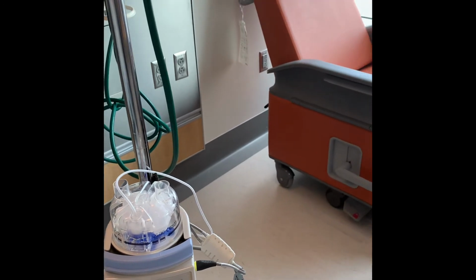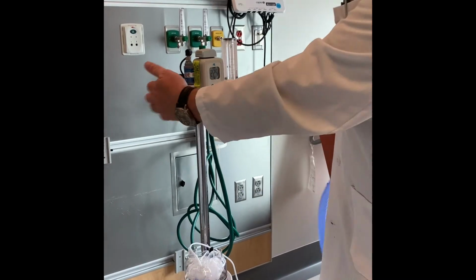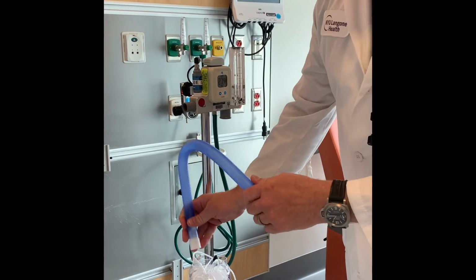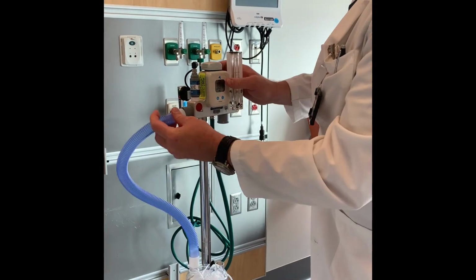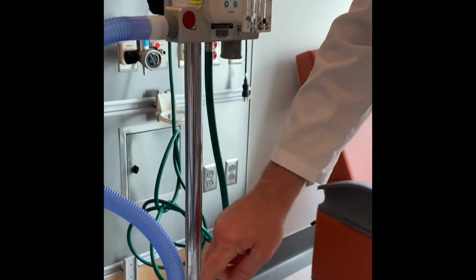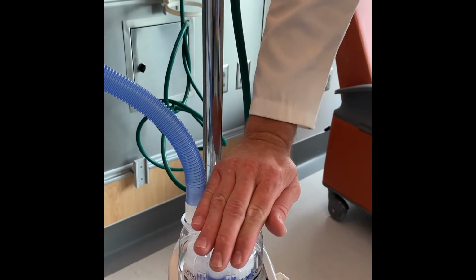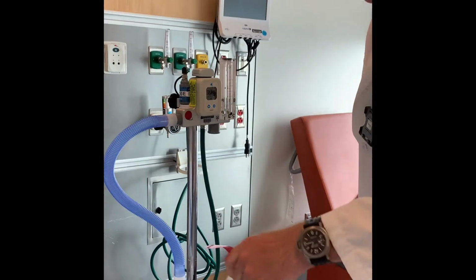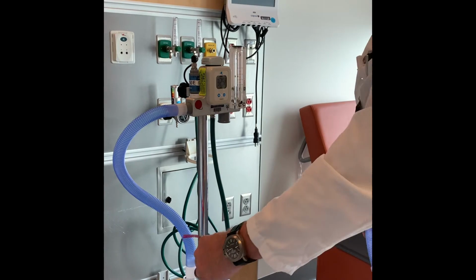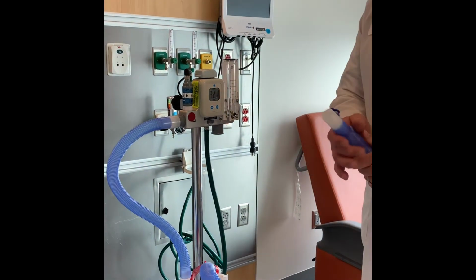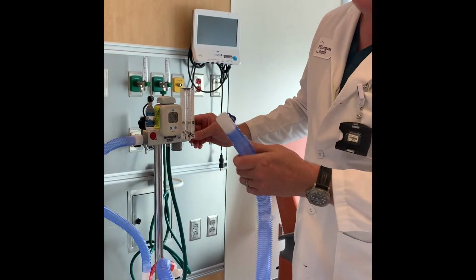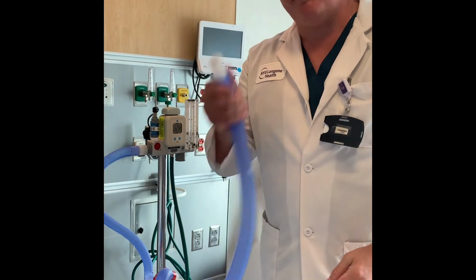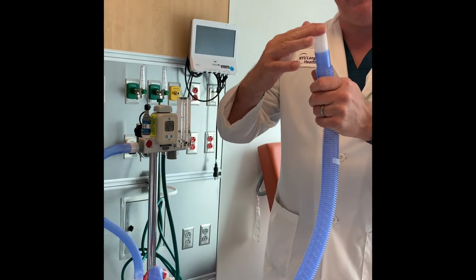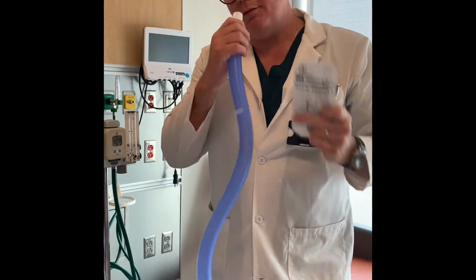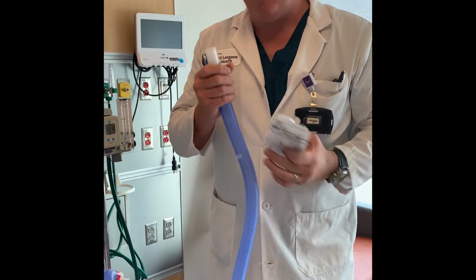Then, as you see, the air comes out of here. So we want to feed the air from the device into the humidification chamber. So now the air is coming from here. Now we want to deliver it to the patient. It doesn't matter which hole it goes into, you can switch them. Now, you can't see, but I'm telling you, the air is coming off the end of the tube. And this is where the interface, or the cannula, which is right here, plugs into the tip of this device, and the person gets their high flow.